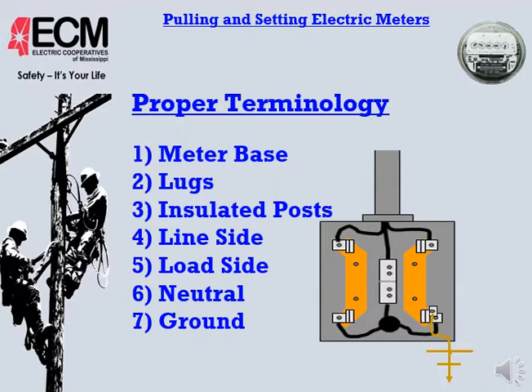If that's the case, then we usually have to change one side of the guts or change the whole meter base entirely. Of course, then you have the line side. That's going to be the top of the meter where the wires come in. The load side, of course, will be the bottom where the wires go out into either a house or a building or a disconnect of some sort. You're going to have your neutral. It's located in the center, the lugs in the center. You'll have neutral lugs on the source and the load side. And of course your ground will be the copper, number 6 copper that comes in, depending on which hole was knocked out when the electrician installed it—could be on the right hand side, the left hand side, or even in the middle, usually from the bottom of the base.